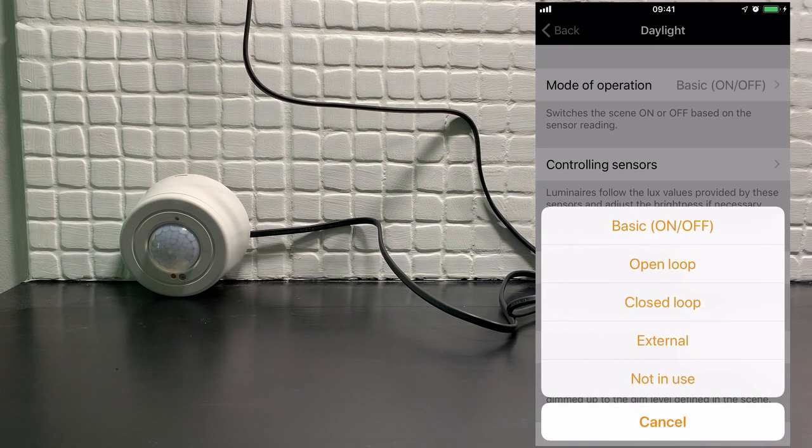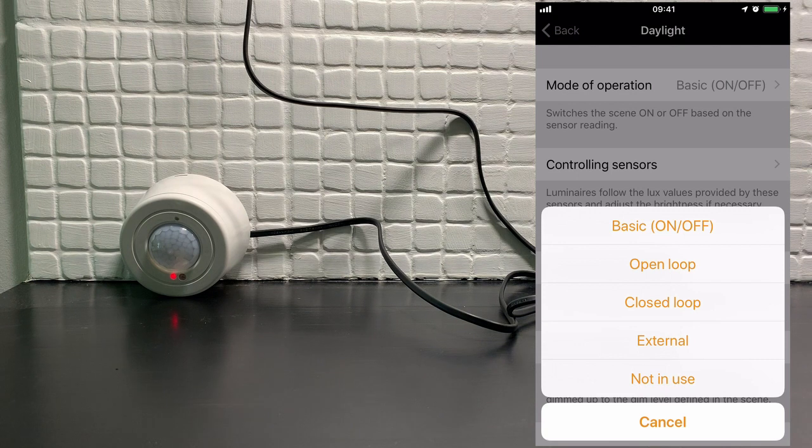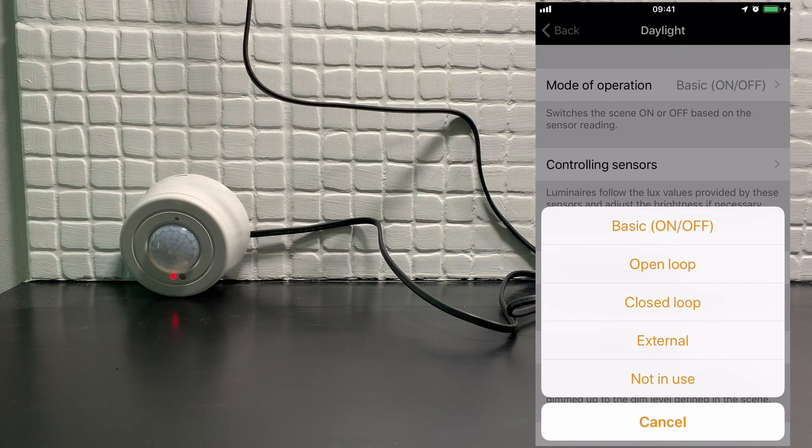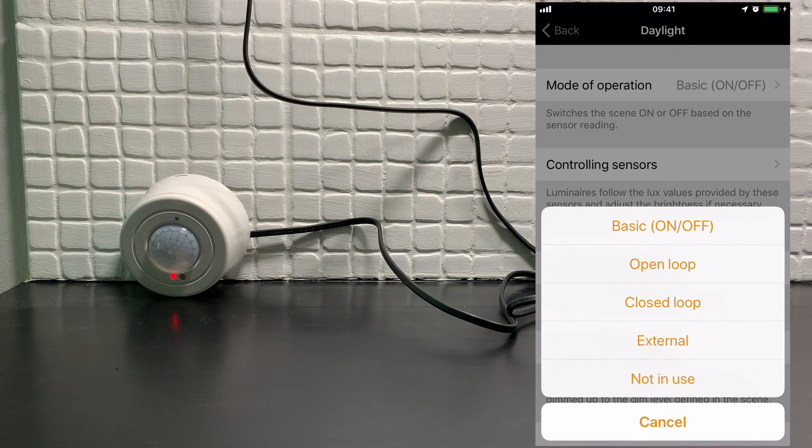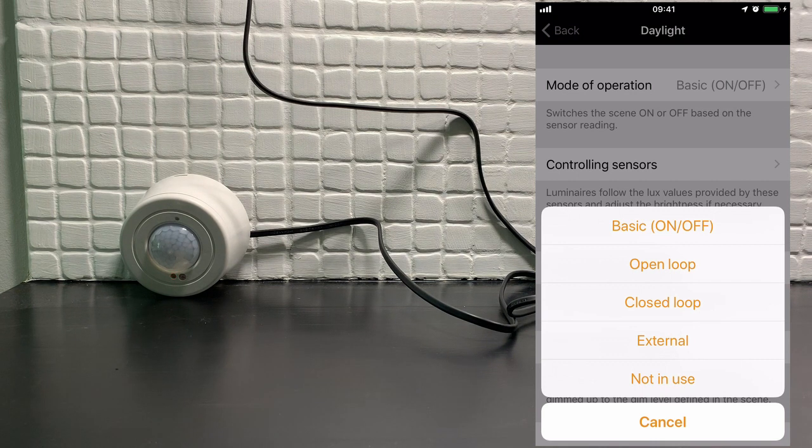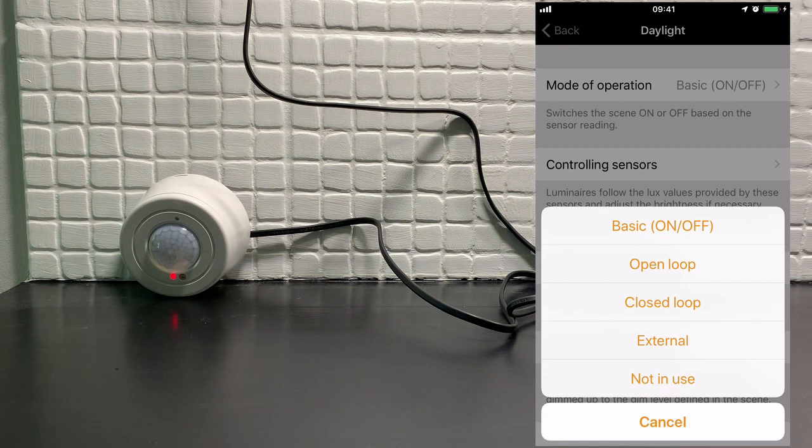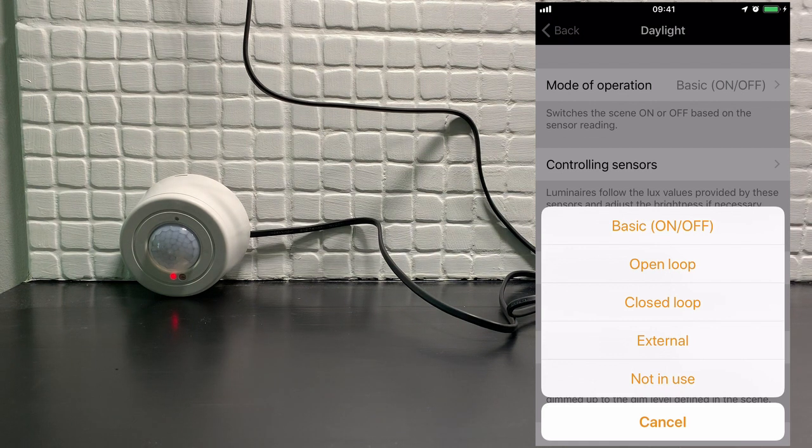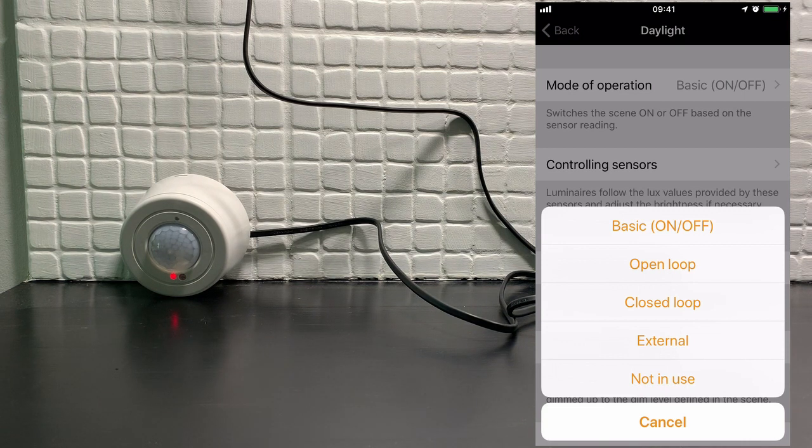The other options are open-loop and closed-loop. These two differ slightly in that an open-loop is designed to sense natural daylight coming into a building, so a sensor would normally be placed externally to the room. Closed-loop is when a sensor is contained within the same area as the luminaire, so it's internal.